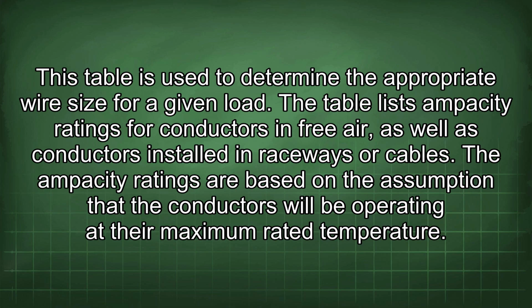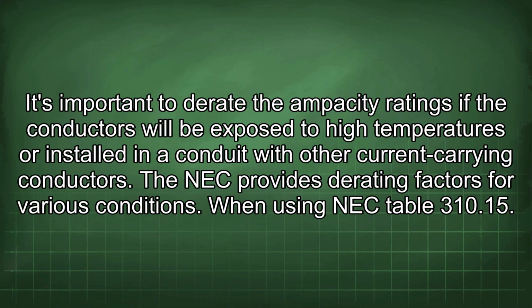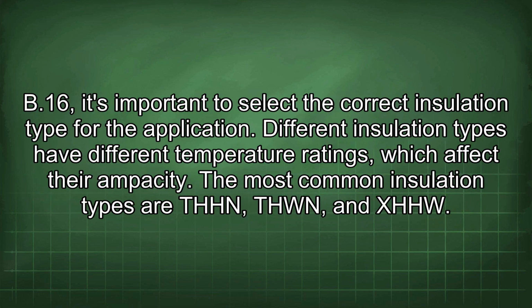The ampacity ratings are based on the assumption that the conductors will be operating at their maximum rated temperature. It's important to derate the ampacity ratings if the conductors will be exposed to high temperatures or installed in a conduit with other current-carrying conductors. The NEC provides derating factors for various conditions. When using NEC Table 310.15 B16, it's important to select the correct insulation type for the application. Different insulation types have different temperature ratings which affect their ampacity.